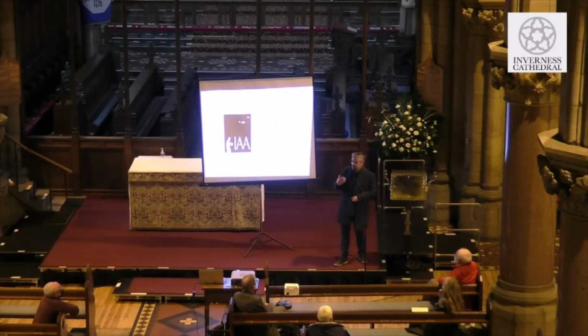Doing nothing is not always a solution, because if you've got uncontrolled ventilation, it's making its way through gaps and corners, and that means that you're getting cold spots, what's called cold bridges, and these are areas where you are going to get problems with mold growth and condensation. And the more insulation that you put into the house, the more these little gaps and paths for air to get through become much more critical, because when you're stopping the moisture getting out in one area, you're concentrating it and focusing it in areas where it can escape. So the more insulation you start putting into the building, the more these areas become critical and need to be thought about carefully.